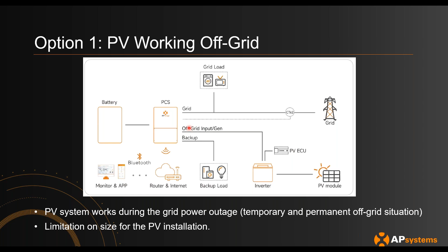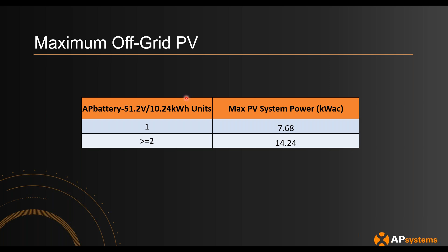This quick graph describes the maximum amount of solar you can put on that port. It's going to be 14 kilowatts AC onto the off-grid port. If you just have one battery, it's going to be half of that. But if you have two of the DC batteries, and I'm not talking about the inverter or the PCS, I'm talking about the batteries, if you have two or more, then you'll be able to put 14. If you just have one, then you'll be able to put 7.6 kilowatts AC. This is the reason why we generally recommend having two of these 10 kilowatt hour batteries.